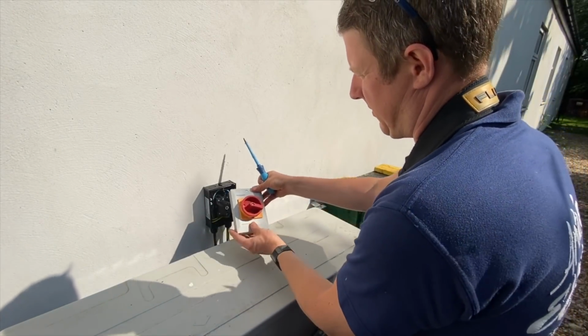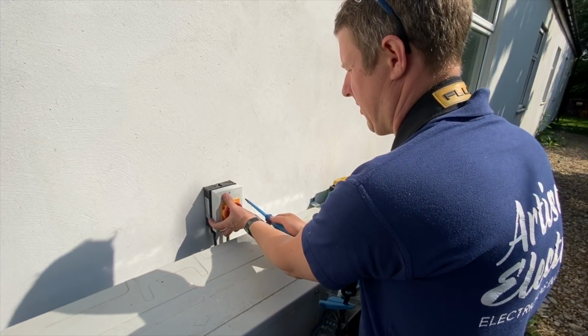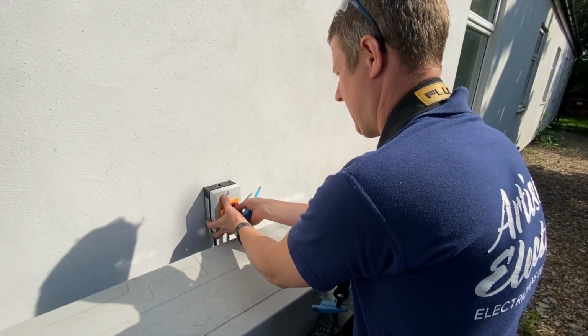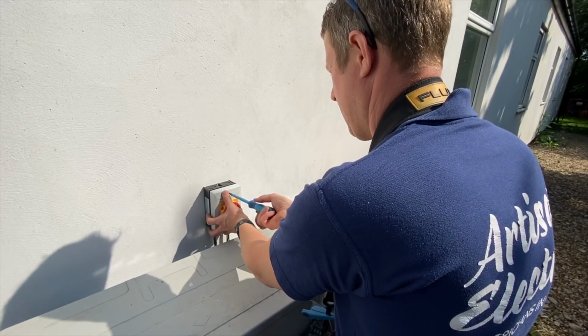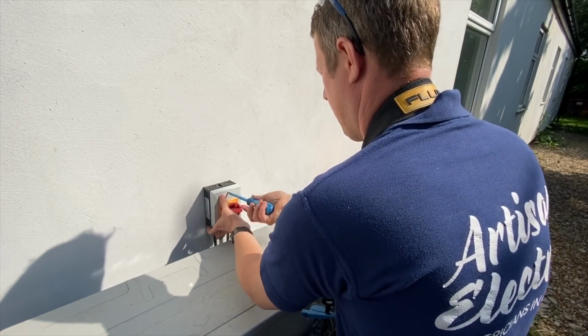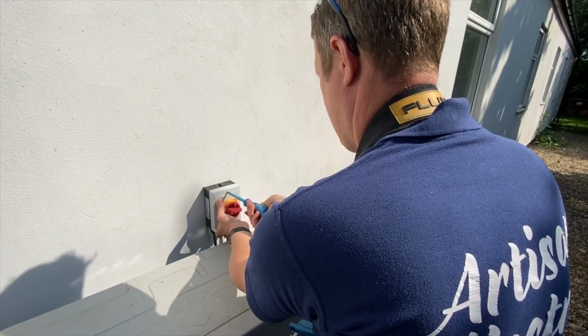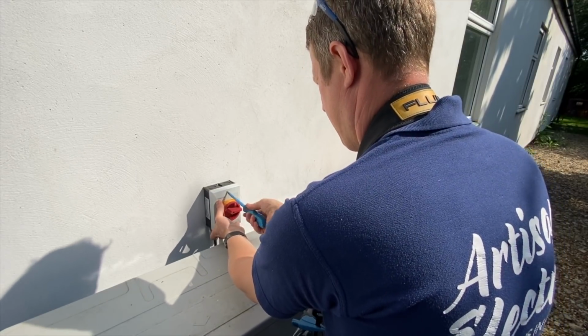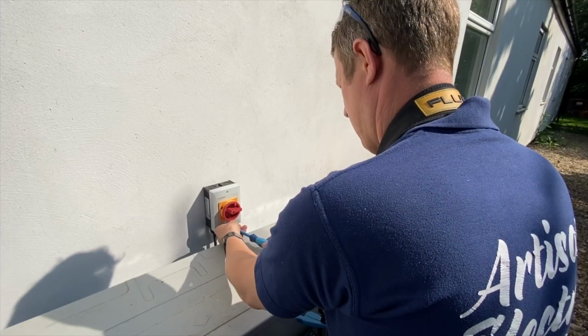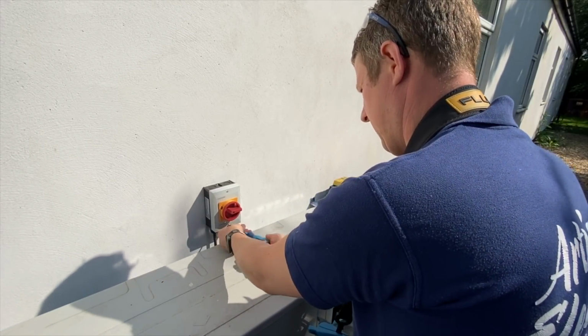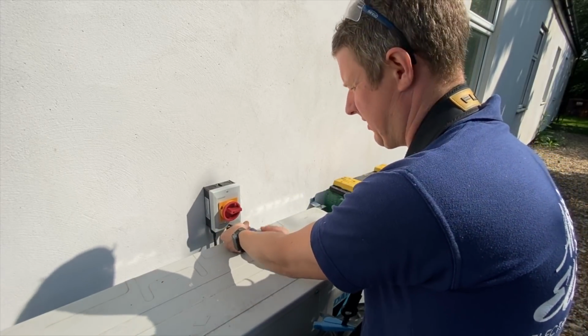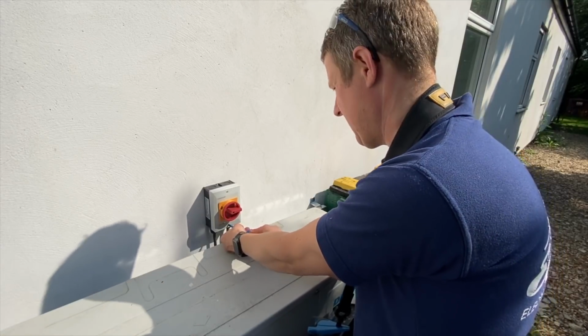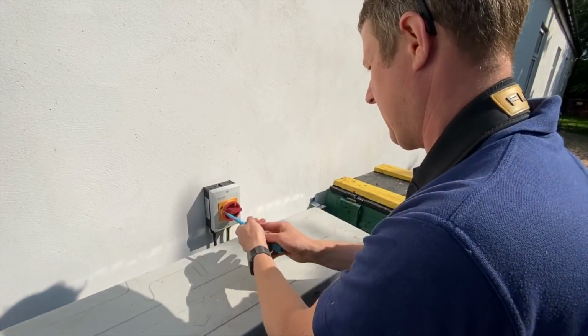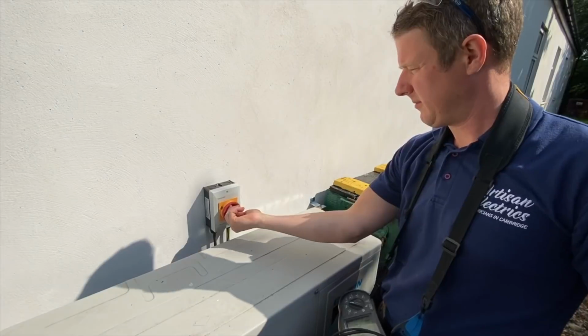That's what it should be, because both of these circuits are the same length, so the readings should be identical really. If they're not, then you question whether there's a weak joint somewhere, a loose connection or something like that. Because the resistance of the cabling is the same and the cable sizes are the same, the readings should be the same if they're the same length.